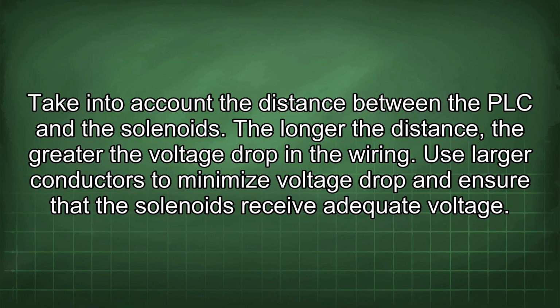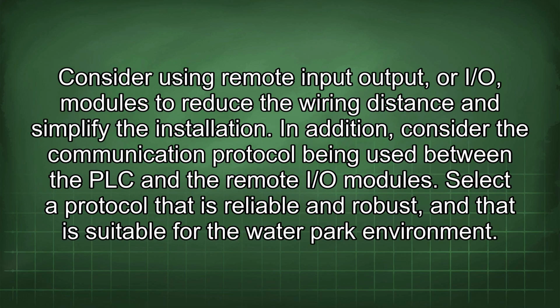Take into account the distance between the PLC and the solenoids. The longer the distance, the greater the voltage drop in the wiring. Use larger conductors to minimize voltage drop and ensure that the solenoids receive adequate voltage. Consider using remote input-output, or I/O, modules to reduce the wiring distance and simplify the installation. In addition, consider the communication protocol being used between the PLC and the remote I/O modules. Select a protocol that is reliable and robust, and that is suitable for the water park environment.